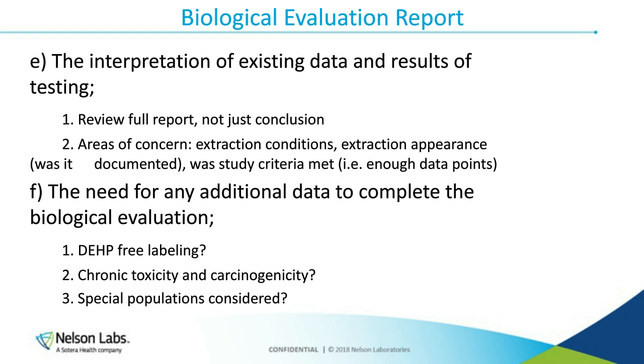So do you need to include some additional targeted testing for labeling? Do you have special populations, a special target organ that needs to be addressed as well, especially if you're doing neural application devices? The data for that type of contact is very limited. So it becomes a very customized project that we end up developing. So we want to make sure we've addressed all of that and discuss it here in the biological evaluation report as well.